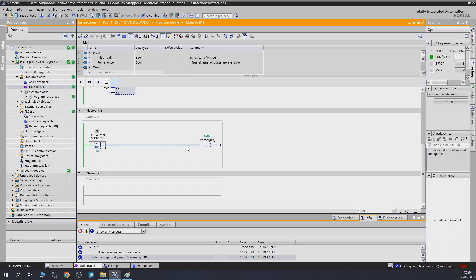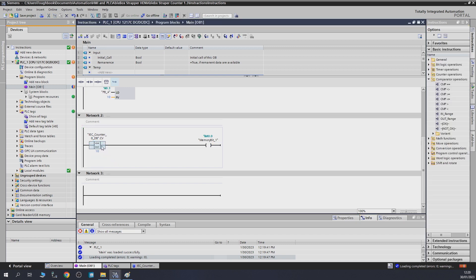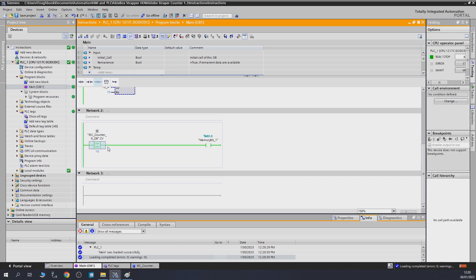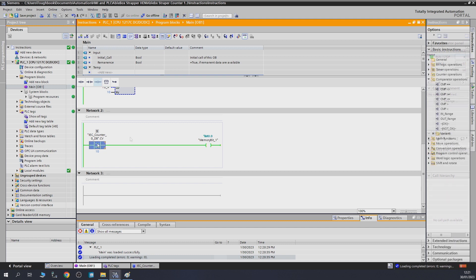Next up let's check out Less or Equal. After updating the block, a value of 9 clearly keeps the output on. As soon as we go above 10 — because it is neither less than nor equal to 10 — the output goes off. But if the value is 10 or below, the output stays on. That is Less or Equal.